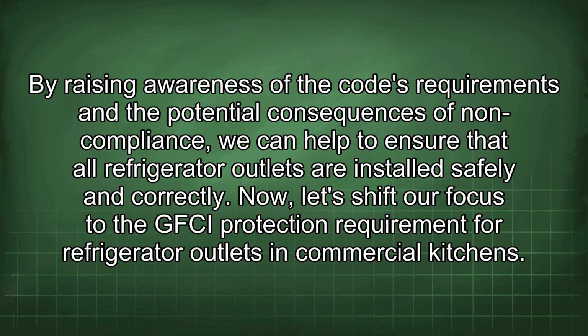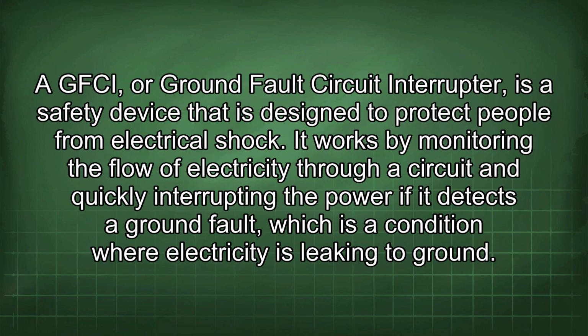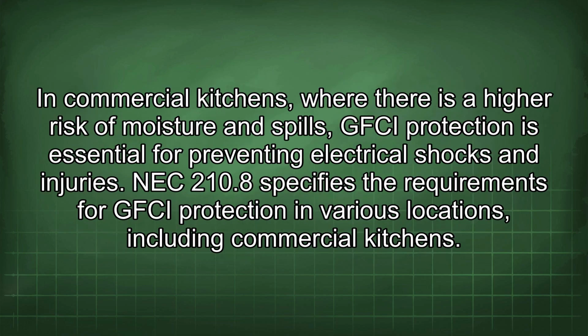Now let's shift our focus to the GFCI protection requirement for refrigerator outlets in commercial kitchens. A GFCI, or ground fault circuit interrupter, is a safety device that is designed to protect people from electrical shock. It works by monitoring the flow of electricity through a circuit and quickly interrupting the power if it detects a ground fault, which is a condition where electricity is leaking to ground. In commercial kitchens, where there is a higher risk of moisture and spills, GFCI protection is essential for preventing electrical shocks and injuries. NEC 210.8 specifies the requirements for GFCI protection in various locations, including commercial kitchens.